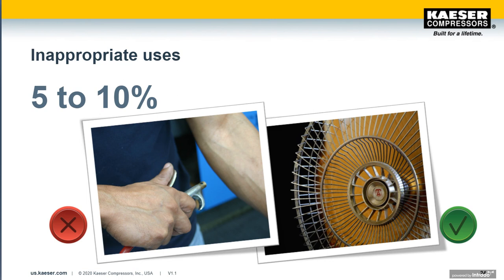So inappropriate uses, I think we mentioned a few, would be any time you're using compressed air when you could use an alternate means to achieve the same effect at a much lower overall cost, or lower environmental impact, like noise or smell, or for safety reasons. We find those to be around 5 to 10% of the demand is actually used for inappropriate uses. There may be some more with some very creative people, but this is roughly the average.